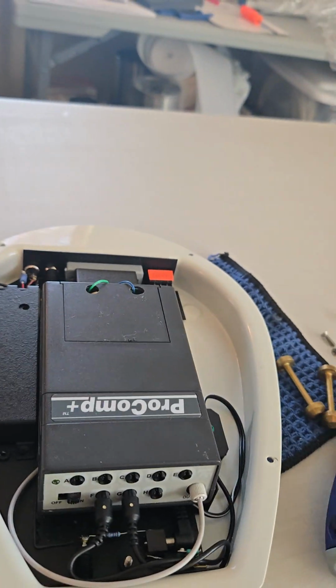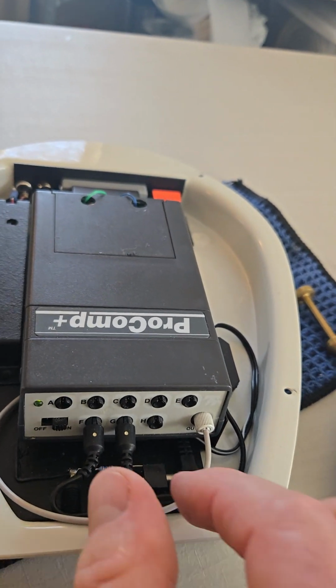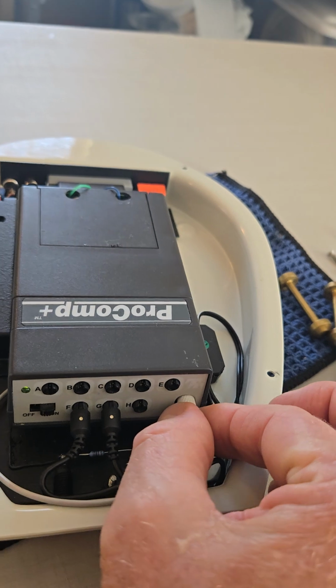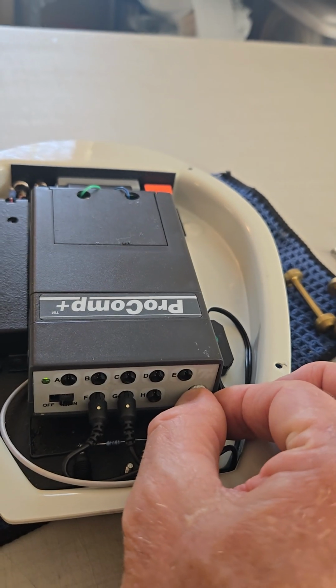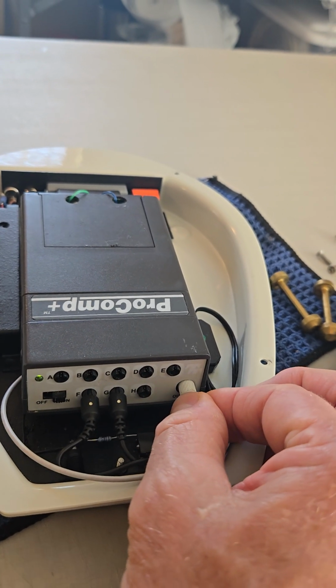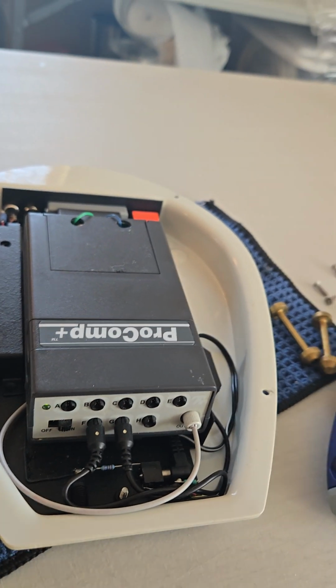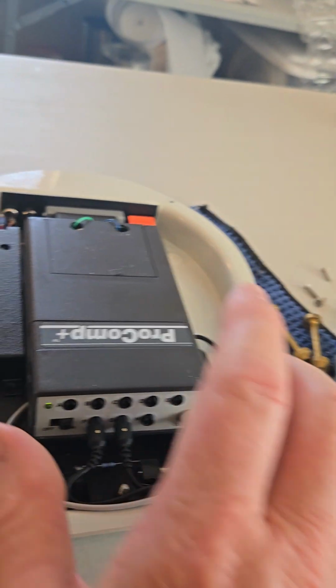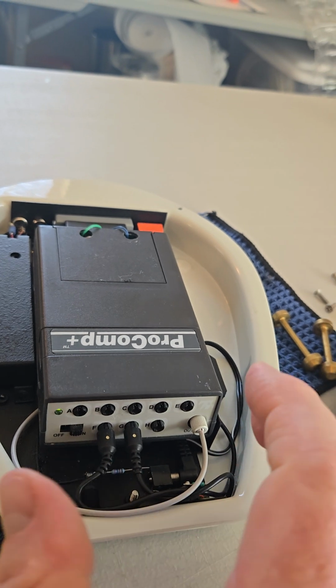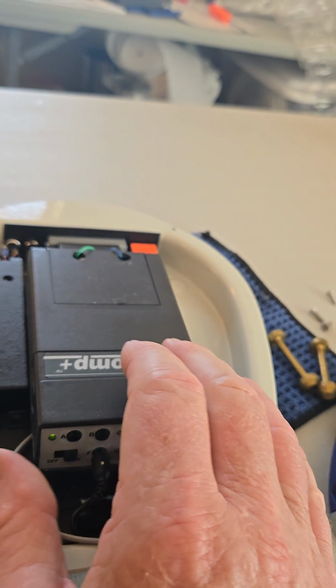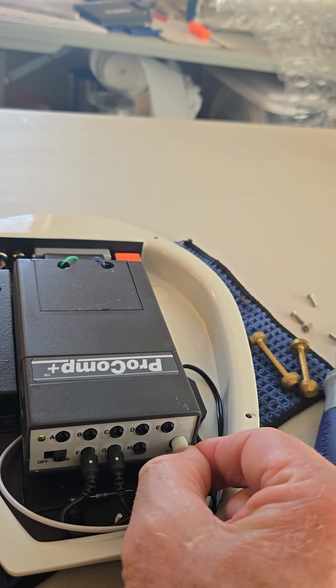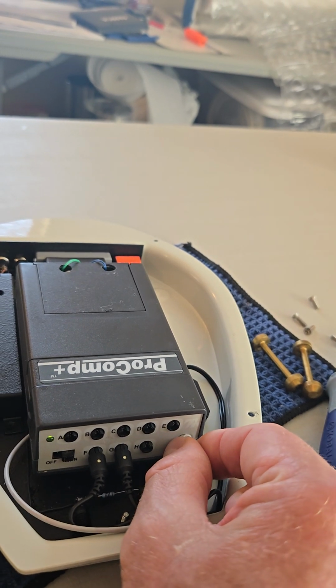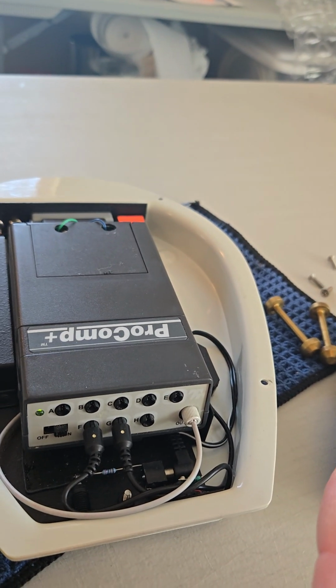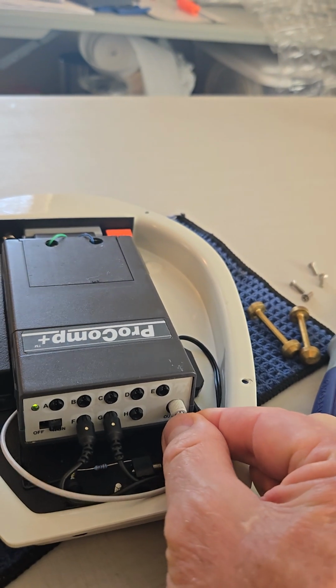So each time you start off by unplugging the sensors, loosen the collar on the fiber optic cable and pull the fiber optic cable out. Then slide the thing out, put your batteries in, clip the battery compartment back in, slide it back, and put the fiber optic cable back in. I'll tell you where people get screwed up with this, it's mainly this fiber optic connection.